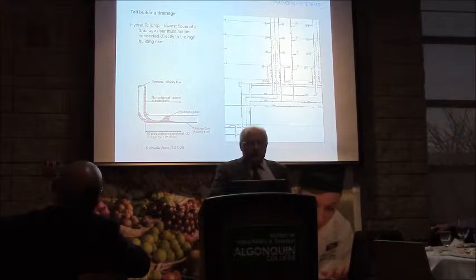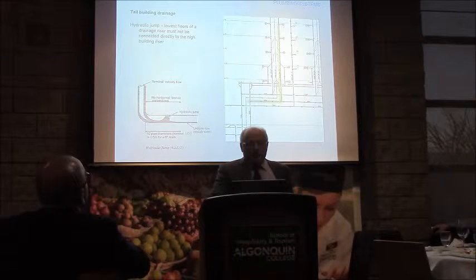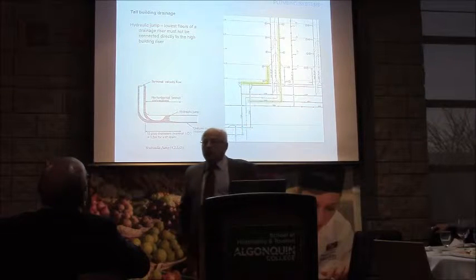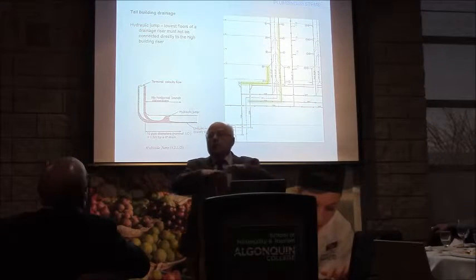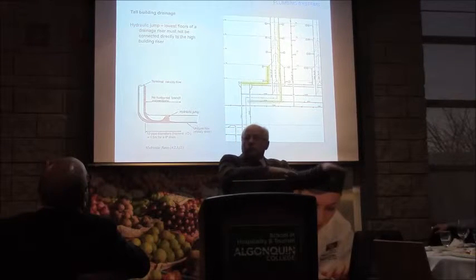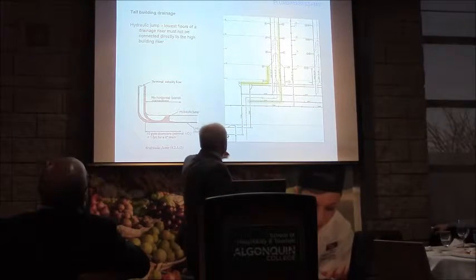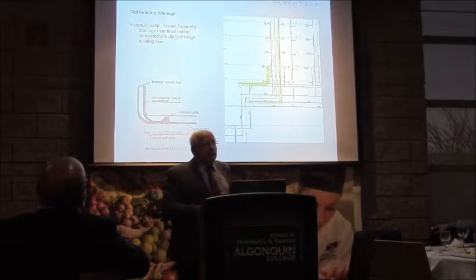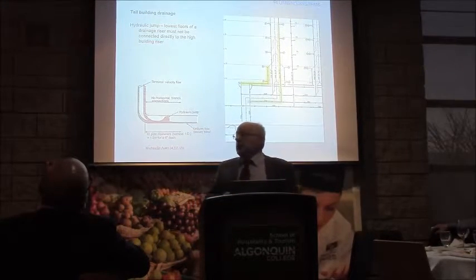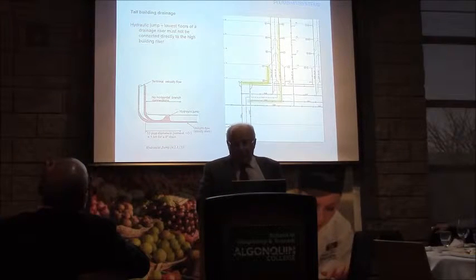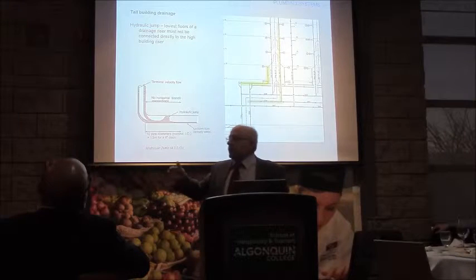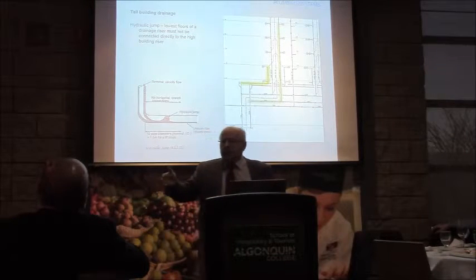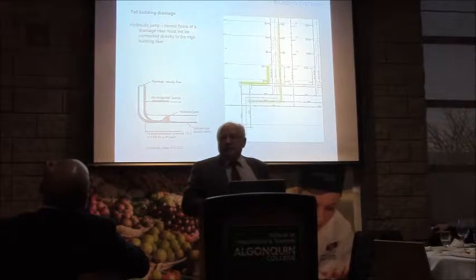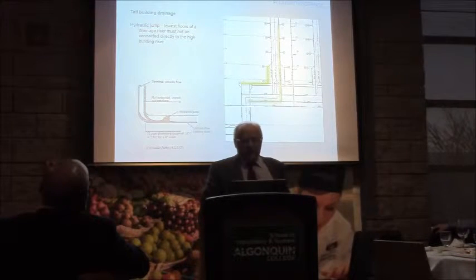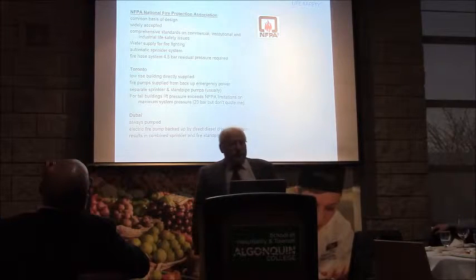So in a system like this, for example, we would take the high pressure line and not connect it to the lowest floor, where we're connecting all the horizontals together, and literally take a horizontal branch farther away and make the final connection down somewhere else because of that hydraulic jump and the issues that can come of that. Once again, we're following the theme, right? We were pressure washing, then we were scalding, and now we were doing something else to the poor person on the facilities. NFPA, we're going on to life safety things.